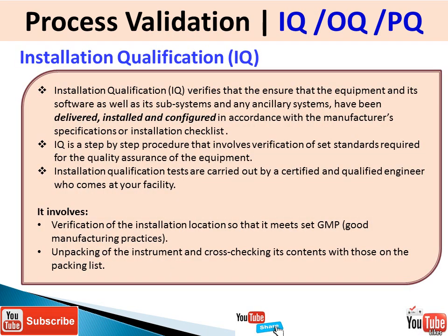Installation qualification basically verifies that the equipment and its software have been delivered, installed, and configured in accordance with the manufacturer's specifications. It is a step-by-step process that involves verification of a set of standards required for quality assurance of equipment. It is normally carried out by a certified and qualified engineer who comes to your facility to perform the installation qualification.